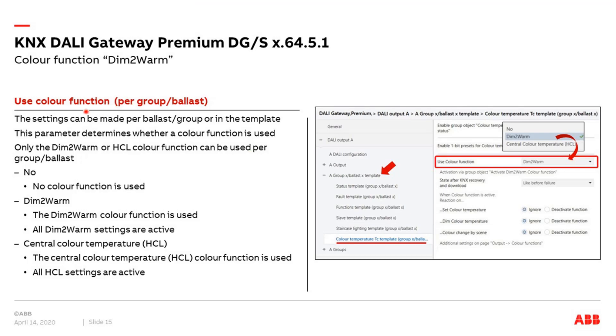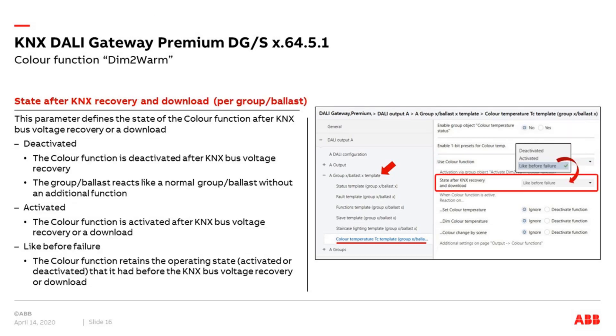Let's begin step by step. In the submenu for group or ballast, go to the template. After setting all status and fault parameters, the last submenu is Color Temperature (Tc) — the template for groups and ballasts. Here, under 'Use color function,' you can select: no color function, Dim2Warm, or central color temperature (HCL). Remember, only one color function can be used per group or ballast. Select Dim2Warm.